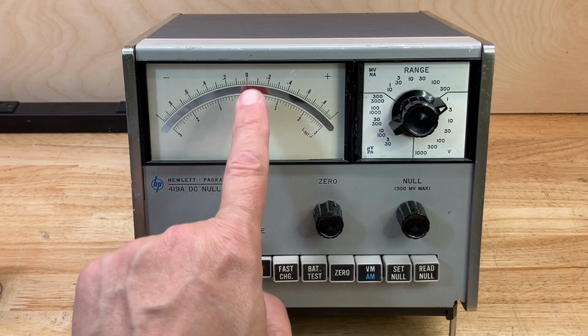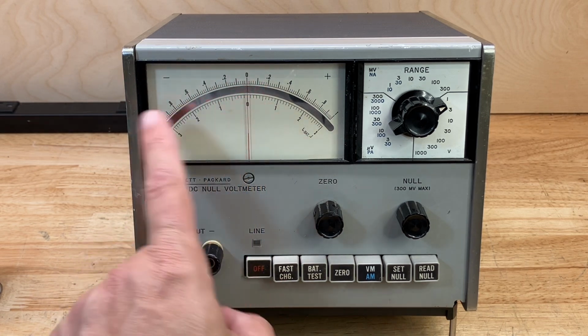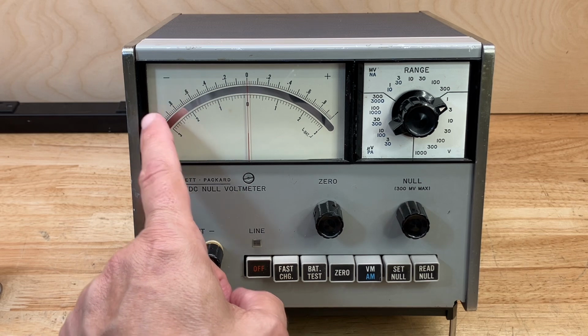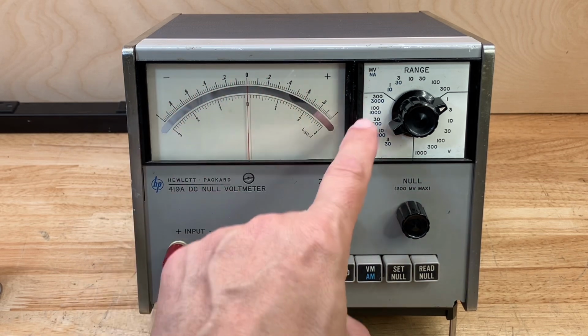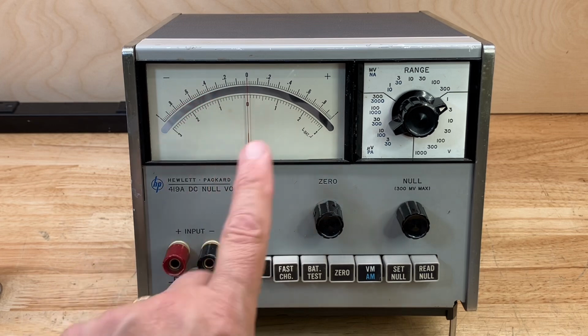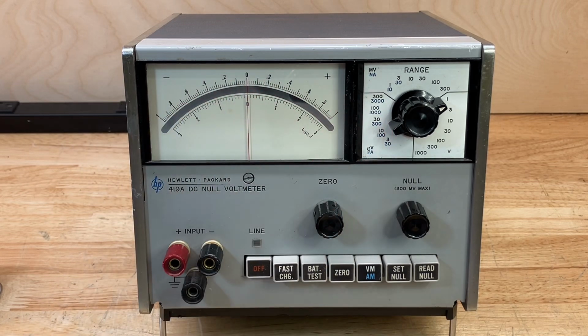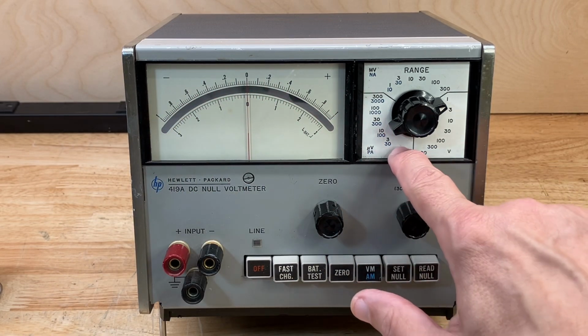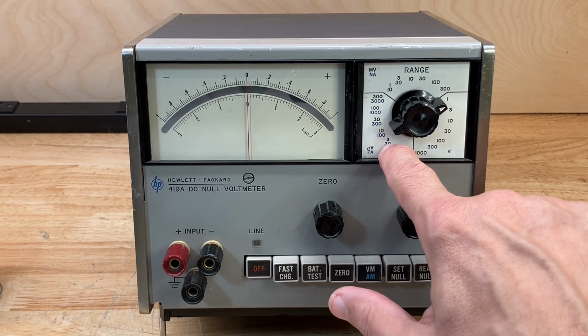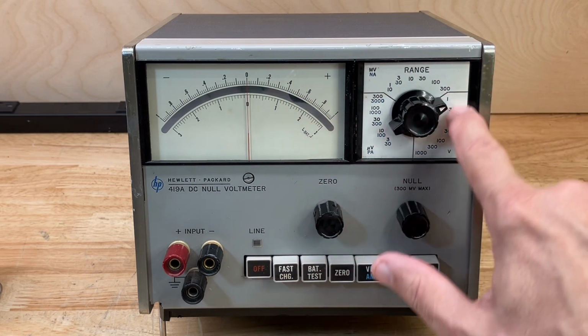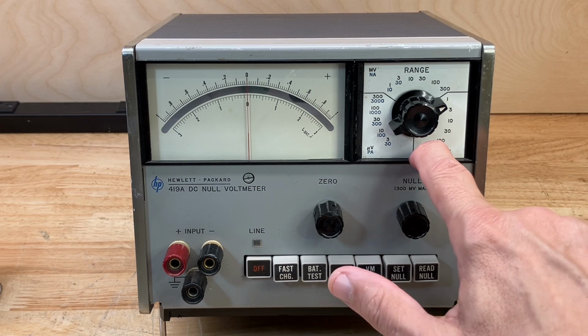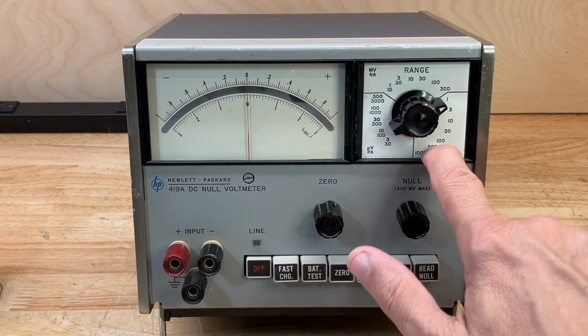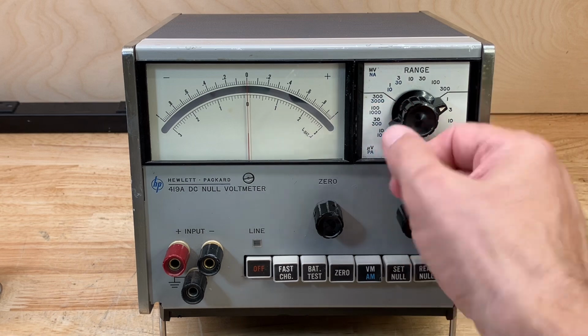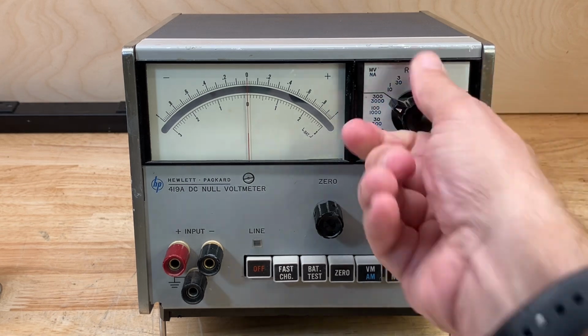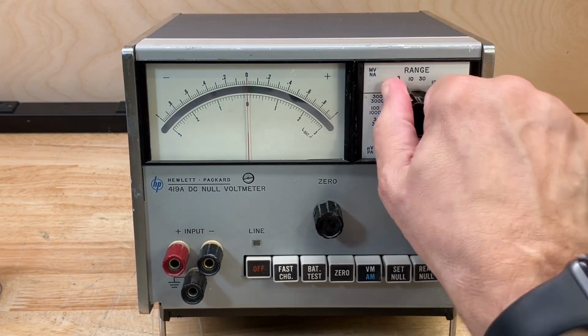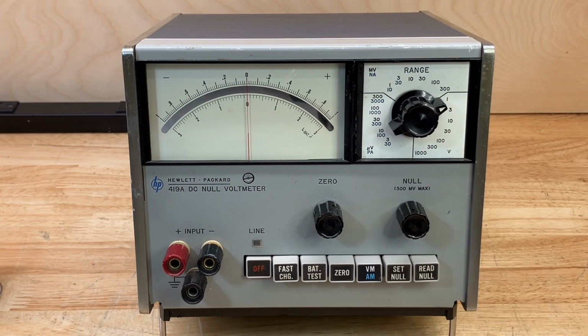The 419A has a zero-centered meter with a -1 to +1 scale or -3 to +3 scale, so it can read both positive and negative voltages. It has ranges from 3 microvolts full scale all the way up to 1000 volts DC full scale, both positive and negative. So there are 18 ranges on this instrument, a very wide range of measurement capability with the DC Null Voltmeter.